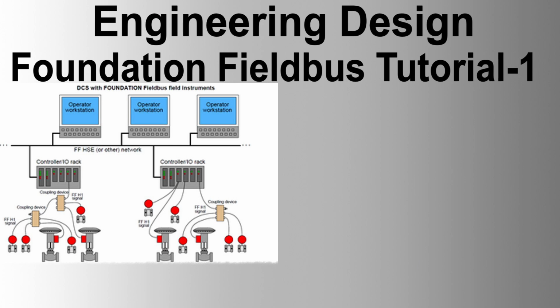Data link PDUs. Table A3 summarizes data link protocol data units in Foundation Fieldbus: EC, establish connection; DC, disconnect connection; CD, compel data; DT, data transfer; PT, pass token; RT, return token; RI, request interval; PN, probe node; PR, probe response; TD, time distribution; CT, compel time; RQ, round trip time query; RR, round trip time response; CL, claim LAS; TL, transfer LAS; idle.